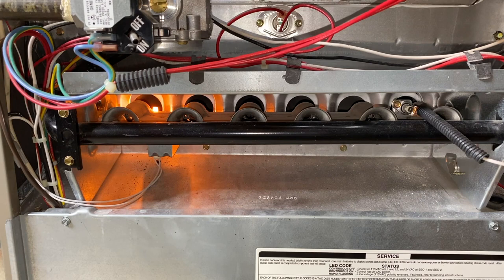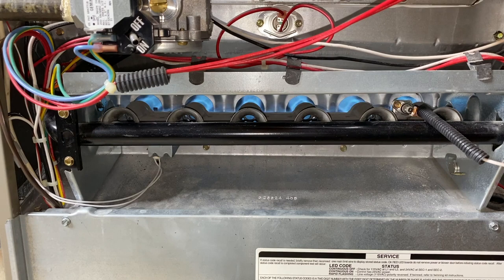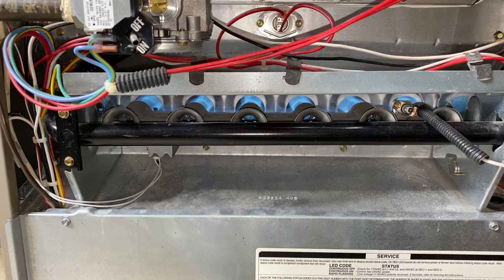At this point all six of my burners are up and running. As you take a close look at the flames themselves, they are perfectly in sync and being directed straight forward in a non-interrupted and efficient forward flow. The blower fan has now turned on to a higher setting, and you see no flames rolling back in this section of the furnace. I'm going to carefully blow into this section of the furnace and interrupt the flow of the burner flames — not aggressively enough to roll them back and turn the furnace off, but just to show you what even a small amount of air being blown in will do to the burner flames.